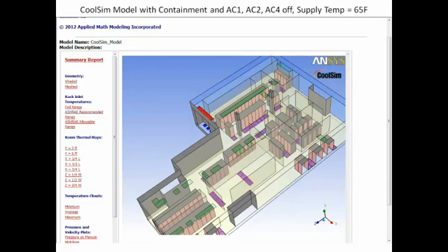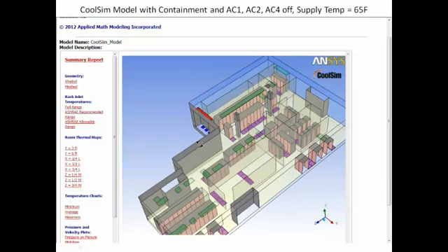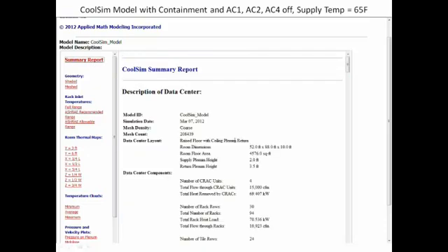We first get the RTI in place, then we adjust airflow to try to make it even, then we begin to increase supply temp. And the reason we're increasing supply temp is because the higher the return temperature, the better opportunity I have for efficiency in the heat rejection system. Generally speaking, for every 1.8 degree Fahrenheit, we get about 3.5% efficiency improvement out of the heat rejection system. That's a good rule of thumb, holds fairly well across all kinds of heat rejection systems, whether they're DX units or chillers. The point simply is to get the return temps up. So let's go see how this worked out.